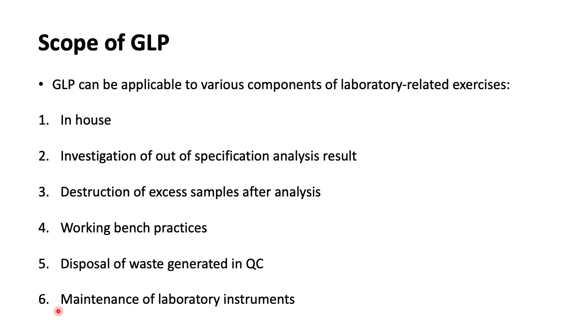Then comes the maintenance of laboratory instruments. Laboratory instruments are mostly electronic devices which require attention at regular intervals. This attention might be in the form of calibration, servicing, or simply cleaning or charging. All of this is taken care of when good laboratory practices are followed. Laboratory instruments are neatly maintained, and there is a log book specifically kept to track who is using the instrument and for what duration.